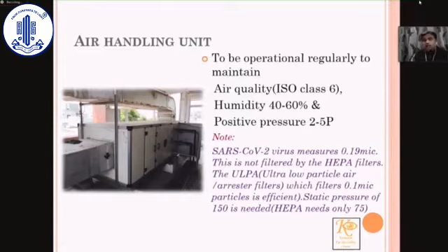HEPA filters because of its 0.19 micron size, and our HEPA filters can only filter particles which are more than 0.3 microns. So if you already have a HEPA filter, you have to change the terminal filter to ULPA, that is ultra low particulate filter. But however, as Dr. Nirmal said, wait for the emergency to shut down, and then you can think about all this.